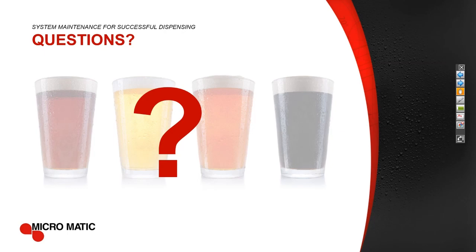Well, once the chemical is in the whole 150 feet, say you have six faucets, if you have enough chemical to fill all of that, then that is the right amount of time. You can certainly soak for longer, and in fact I would encourage it, but if the line is full, the line is full, and your chemical and water ratio is right, 2 to 3% of a caustic nature, then that is enough.